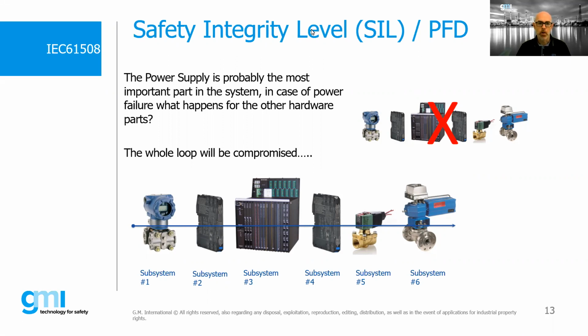And again, power interfaces can be a safety relay, which will then act on a valve and on an actuator, which allow us to bring the system to safety in case of need. The main concept that needs to be understood is that every single element of the SIS must be sized with a SIL level, such as to allow us to obtain the overall SIL of the SIS required.